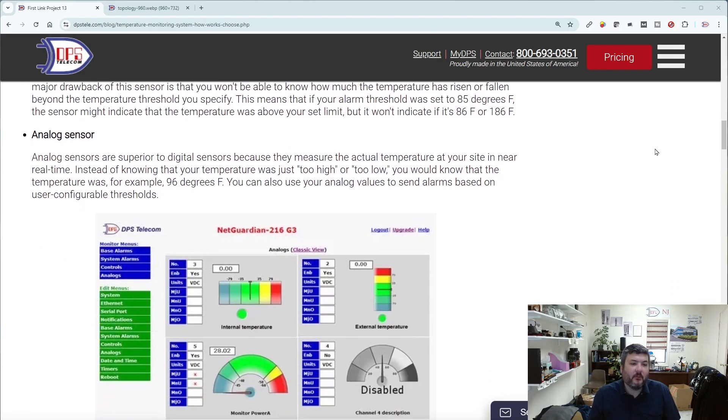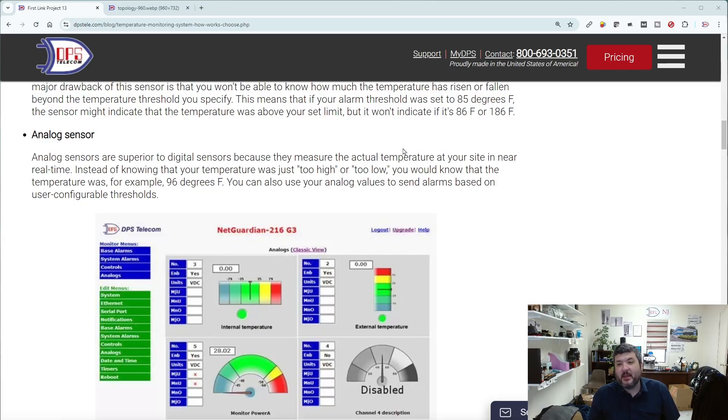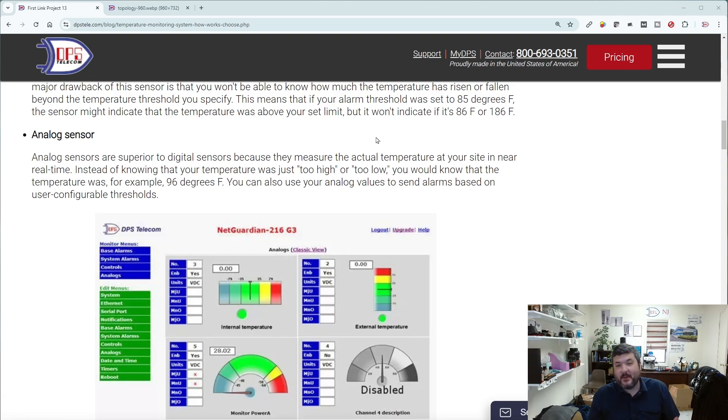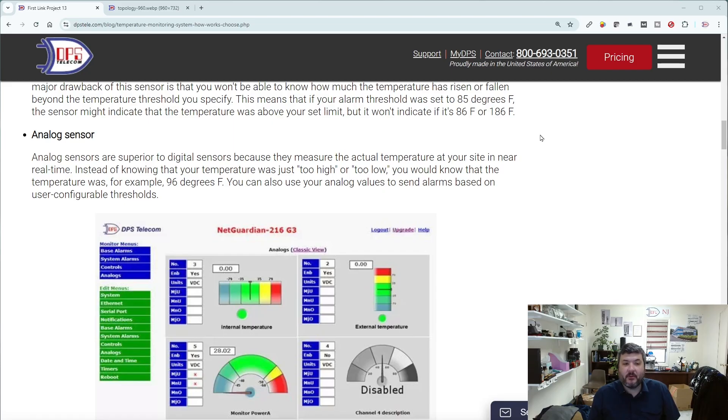If you set it at 80 degrees, you don't know if it's 81 or 181 or 281 degrees. That is less detail than you'll get from other types of sensors. When we talk about the next more advanced type, those are analog sensors. These are going to be sensors that can tell you a specific value. It's like the screen on the front of a thermostat instead of the click, when it tells you it is this many degrees, probably down to the tenth of a degree.